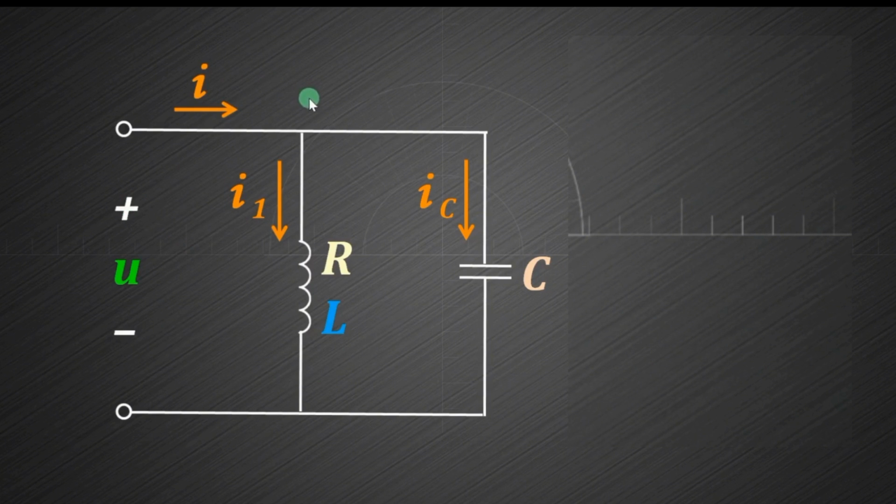The current IC provides reactive power to the load, thus it is also called reactive compensation. This way, the power source can supply less reactive power and more active power, allowing the capacity to be fully utilized and reducing power loss on the lines.